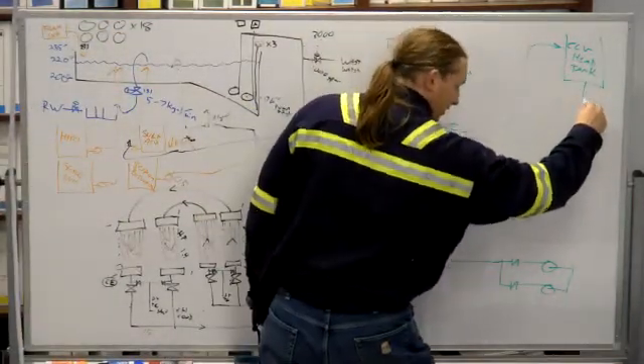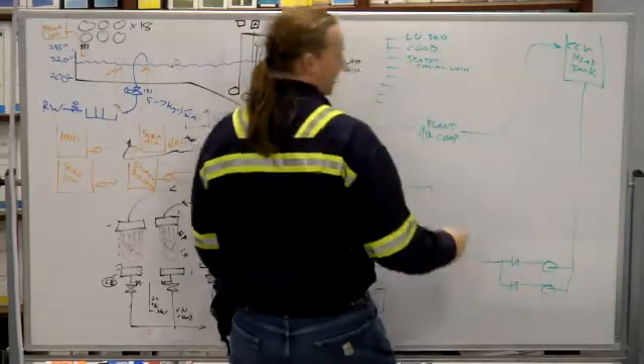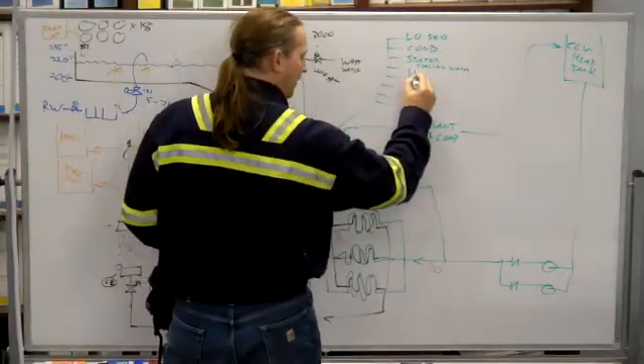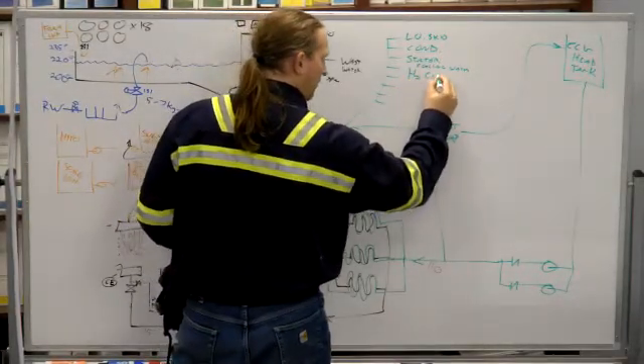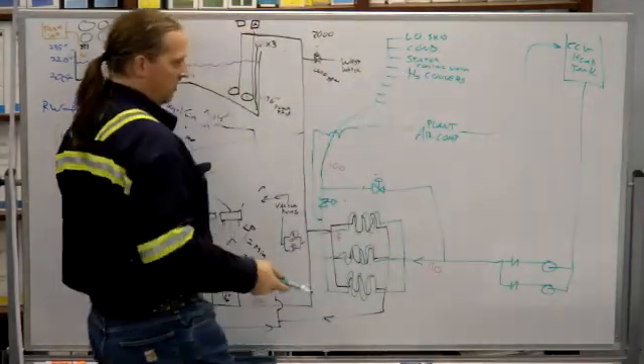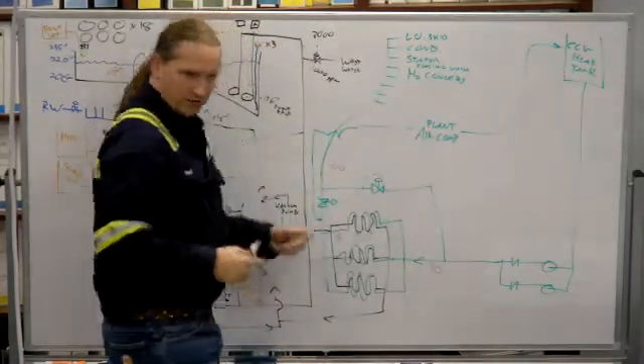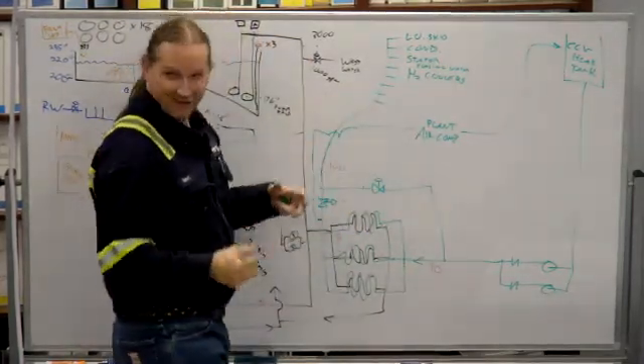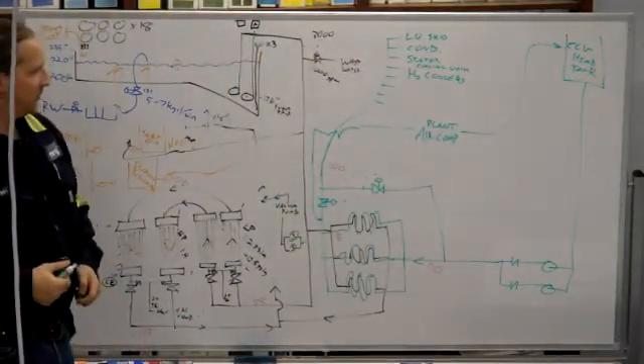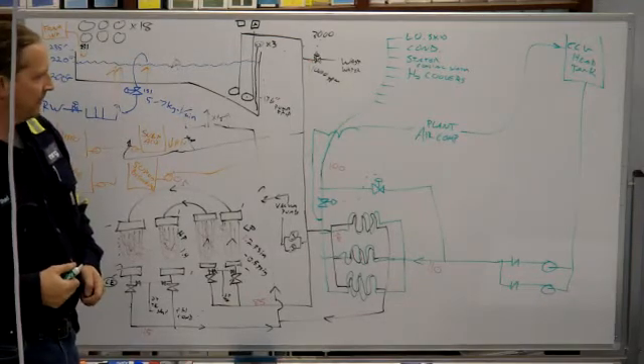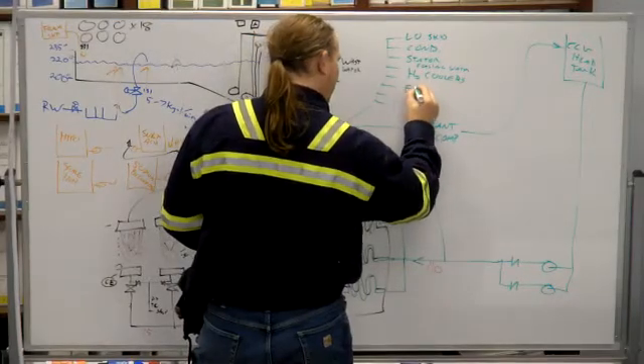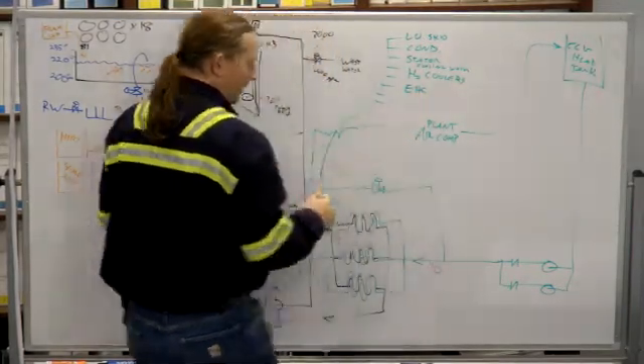So then this head tank goes back down to pumps. Hydrogen coolers. This is also cooling the generator, but this is cooling the rotor part. This is cooling the gas inside the generator, as opposed to cooling the metal bars directly. EHC, consider lube oil skids. EHC is definitely not lube oil, it is hydraulic oil.